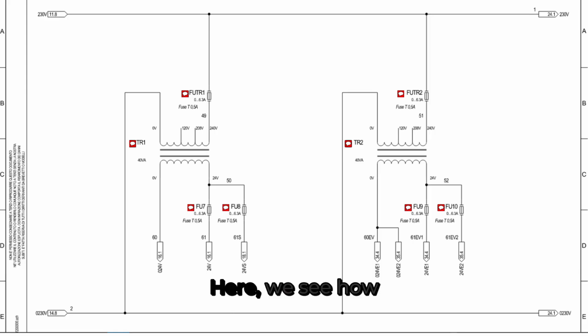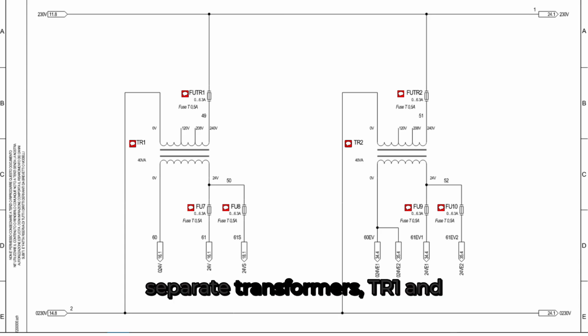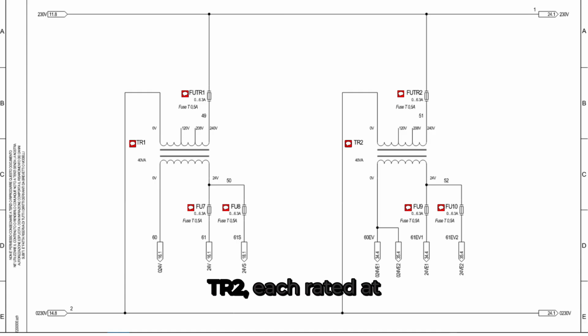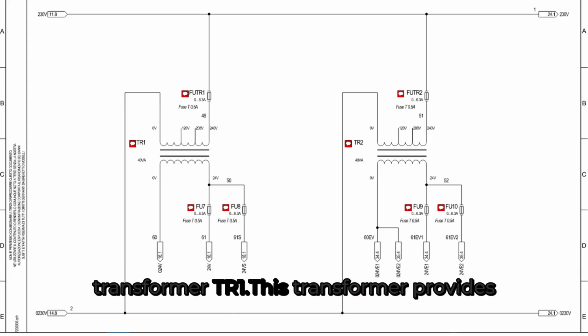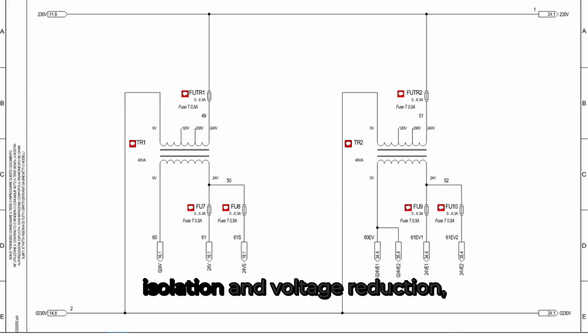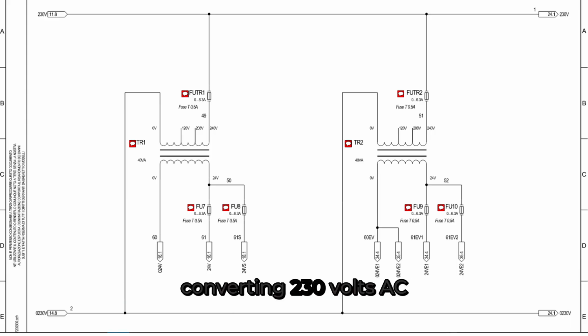Here, we see how the 230-volt supply is stepped down to 24 volts AC using two separate transformers, TR1 and TR2, each rated at 40 VA. Starting from the top left, the circuit begins with the 230V control line feeding into transformer TR1. This transformer provides isolation and voltage reduction, converting 230 volts AC to a safer 24 volts AC, which is used for the system's control and signal components.